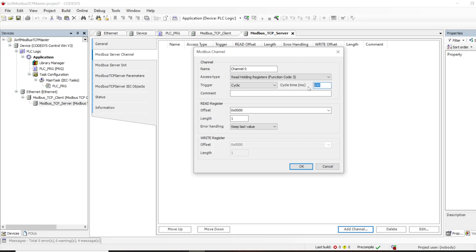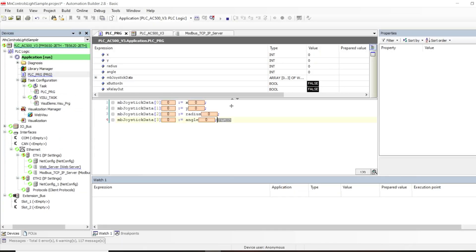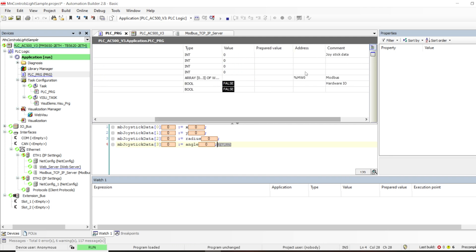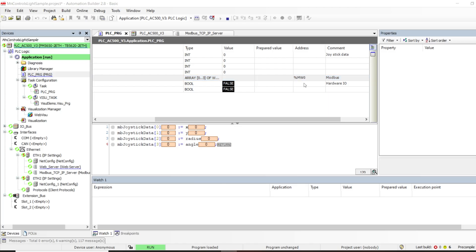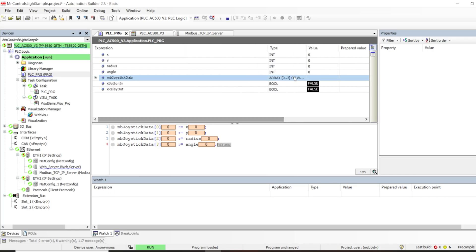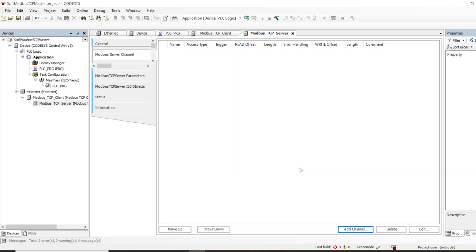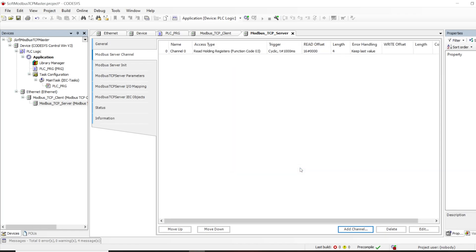The cyclic trigger enables the cycle time parameter, so you configure how fast you want to read — I want to read every one second. You can add a comment if you want, and then define the register offset and count. Based on our server configuration we start reading from register 0 and we want to read four registers. That's it for the channel definition — it defines one Modbus function, and you can add as many channels as you need.